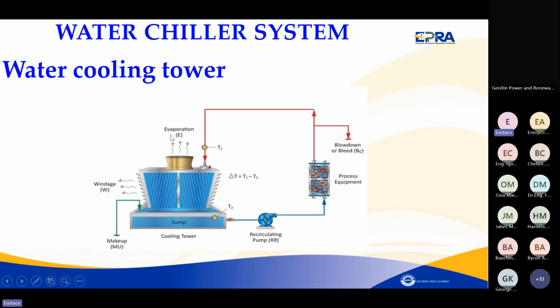This is where you use the cooling towers: you circulate water around, it evaporates and is lost to the atmosphere, then you take back the remaining water, which is a bit cold. But you need to add some makeup water to avoid concentration of particles, and also to make sure it does not drain.